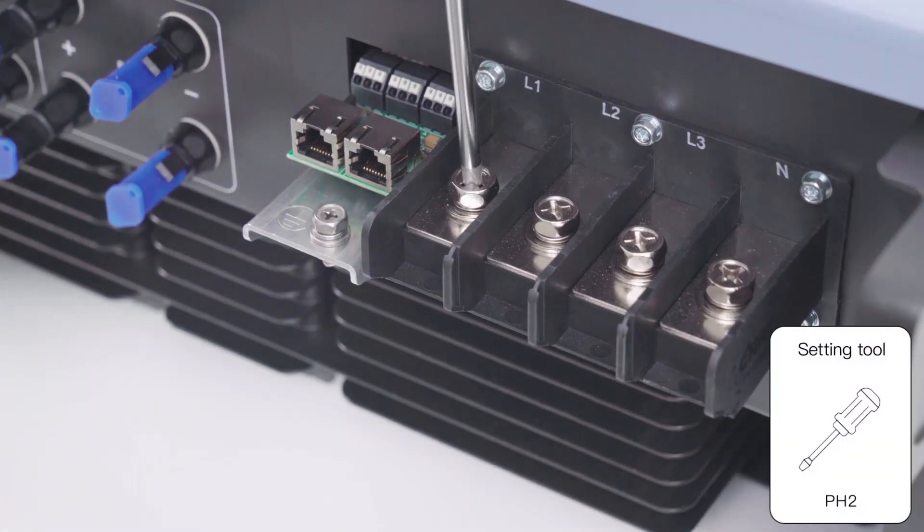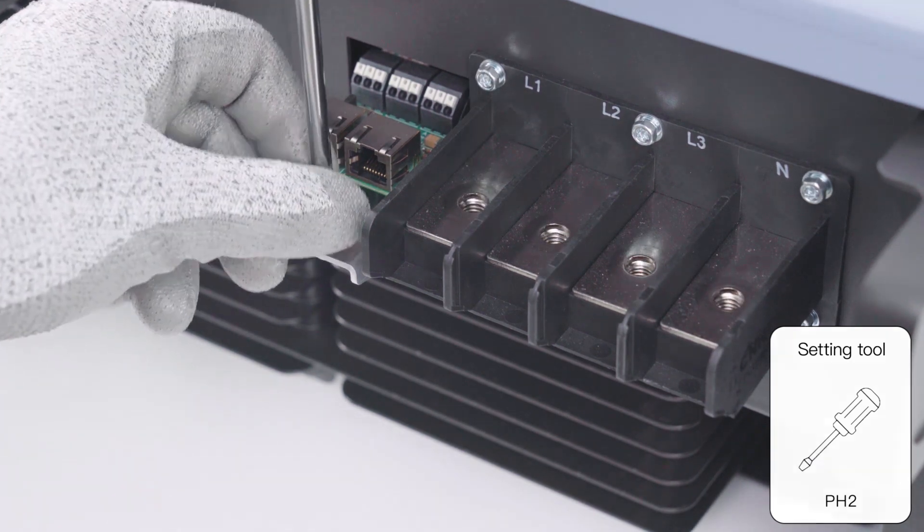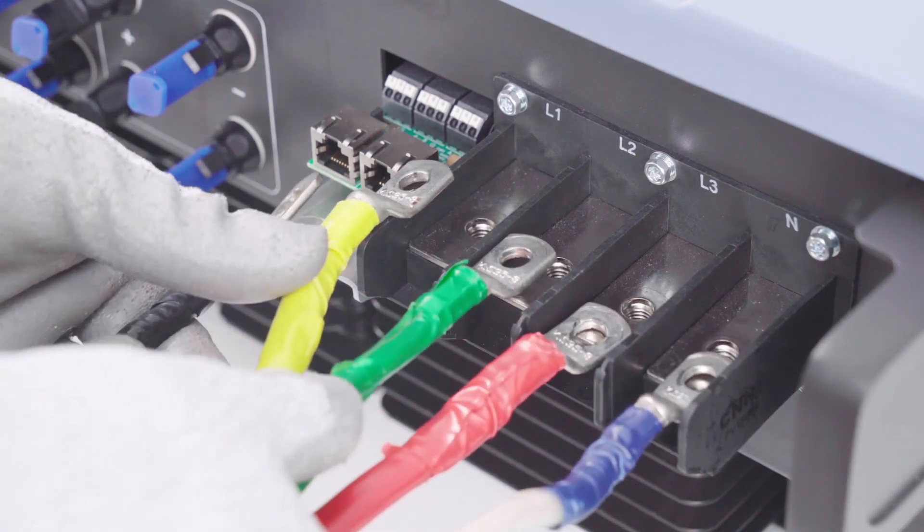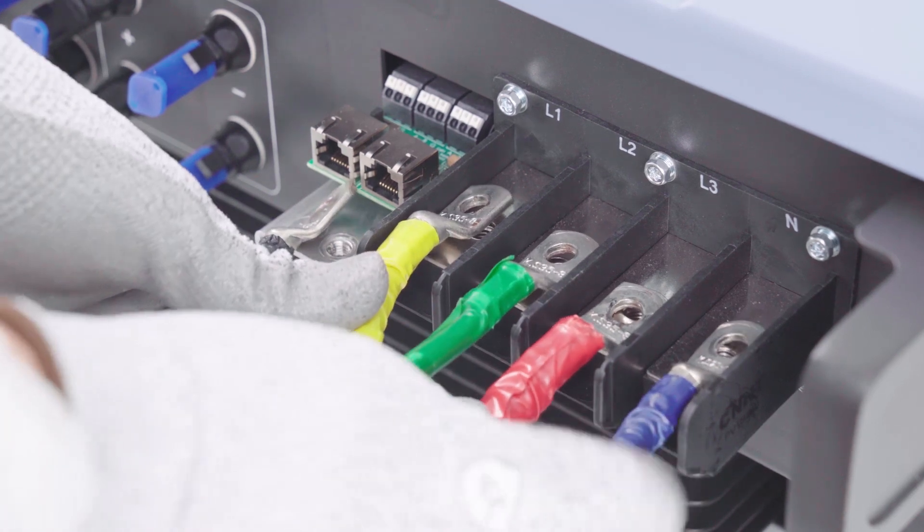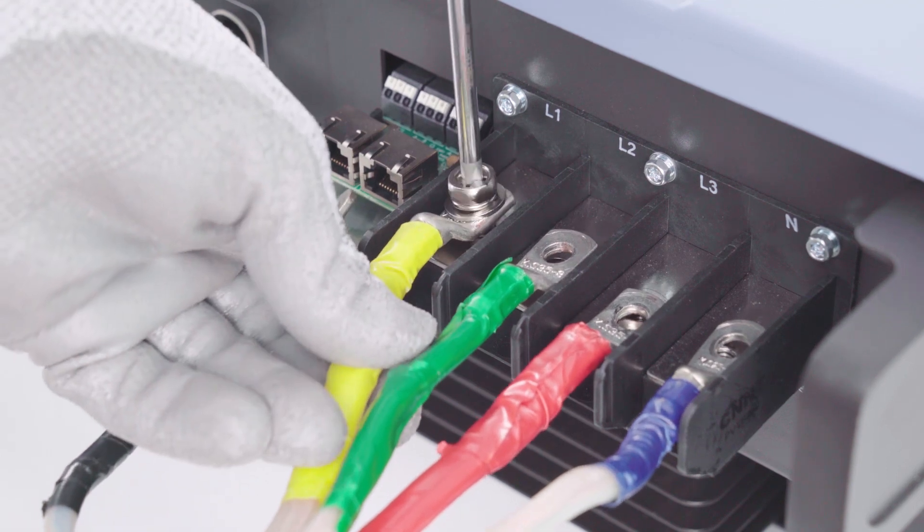Connect the grounding conductor to the protective grounding in accordance with the labeling. Connect N, L1, L2, and L3 to the terminal block for the AC cable according to the labeling.